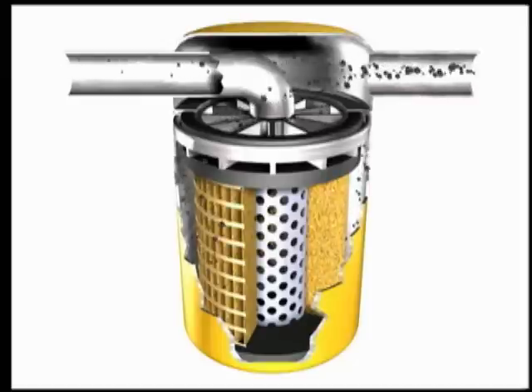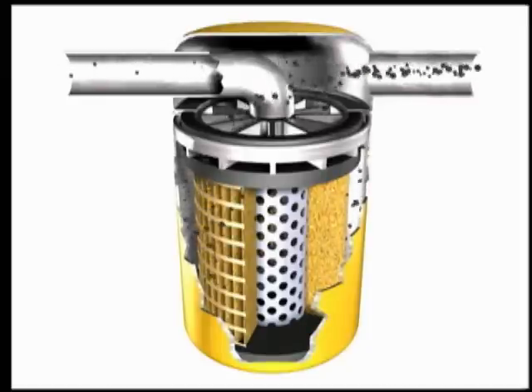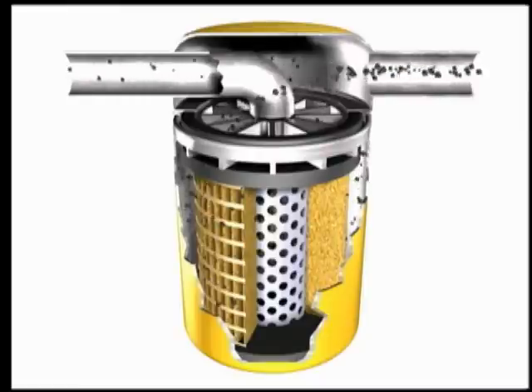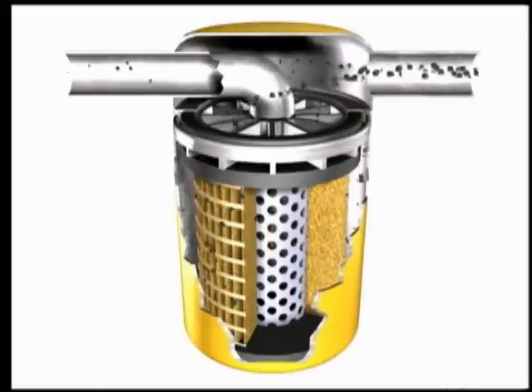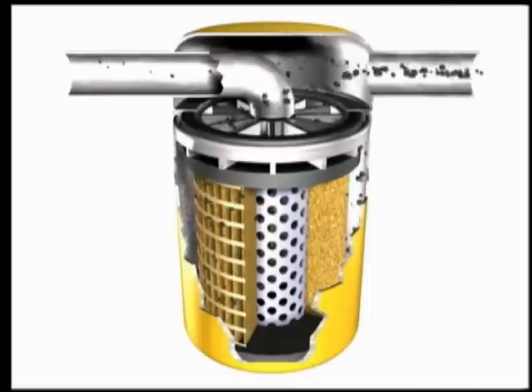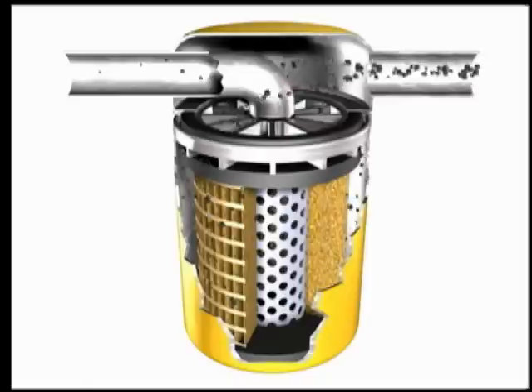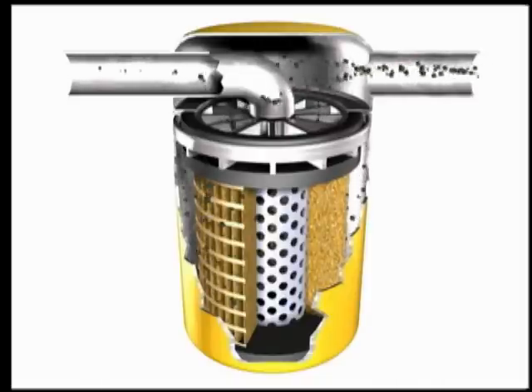All these particles then move on to the filter. Do not assume the filter removes all contaminants in a single pass. As the oil moves through the filter media, many of the particles are trapped, but a few — some large and some small — travel through the media and return to the system through the center tube. Even high-efficiency filters do not remove all contaminants.